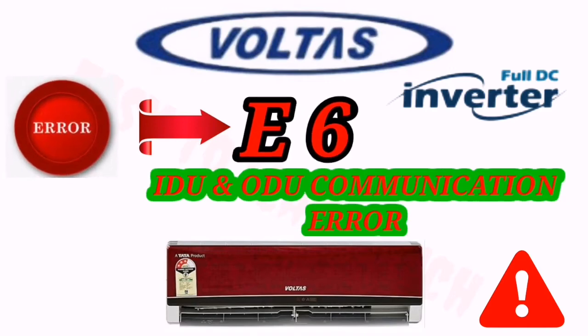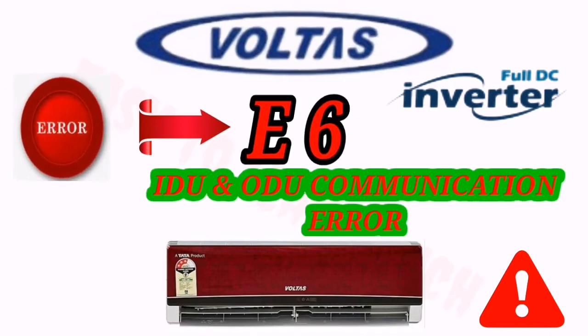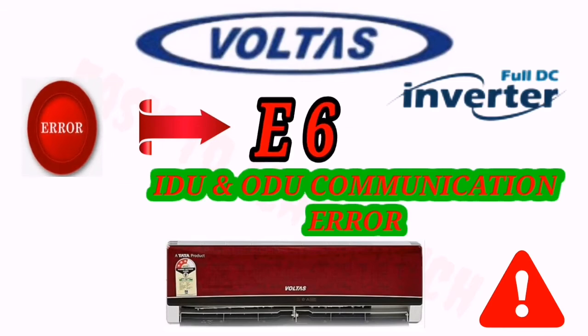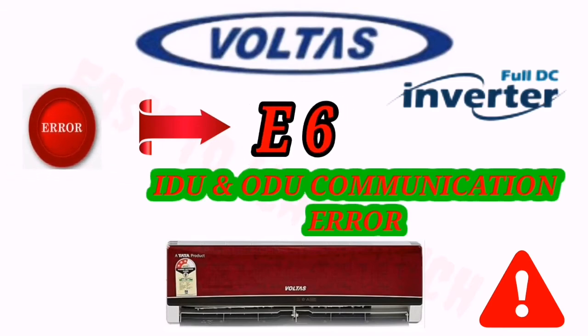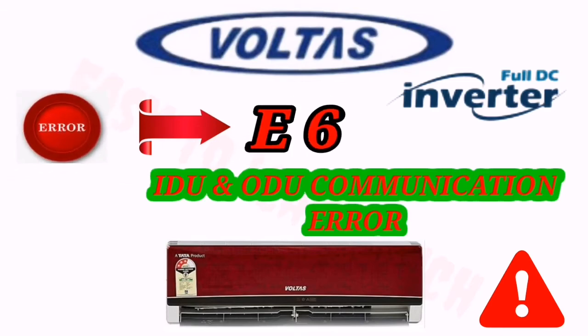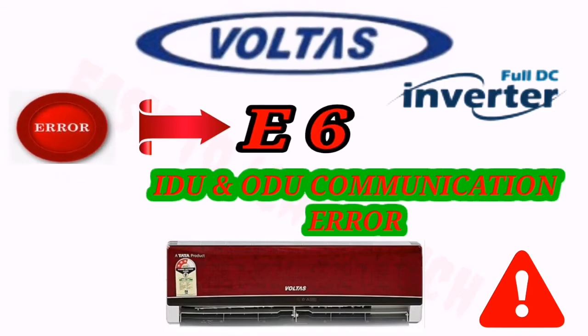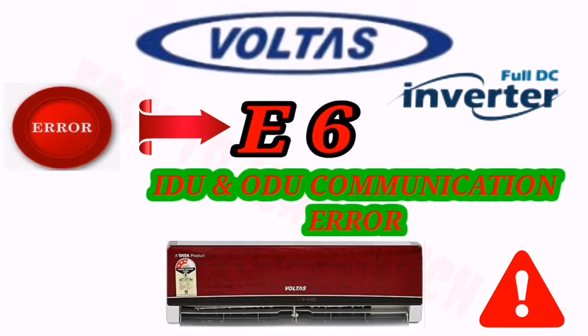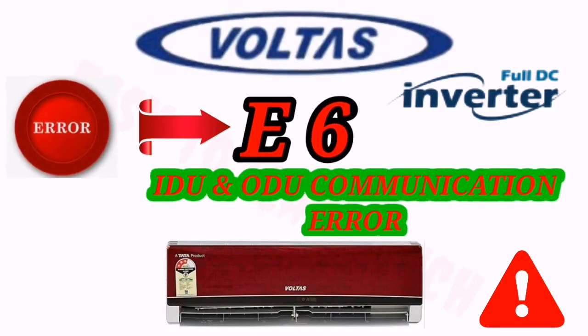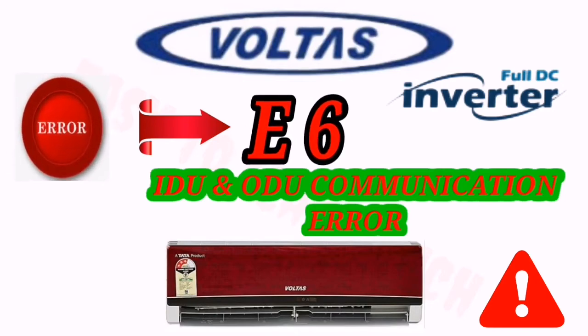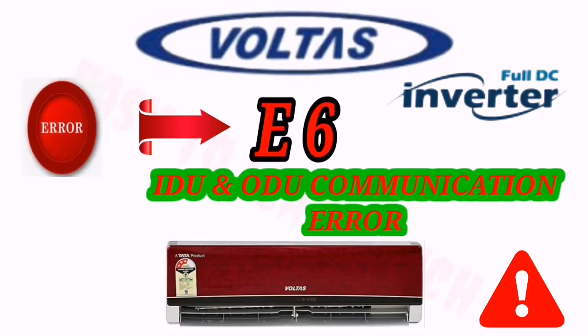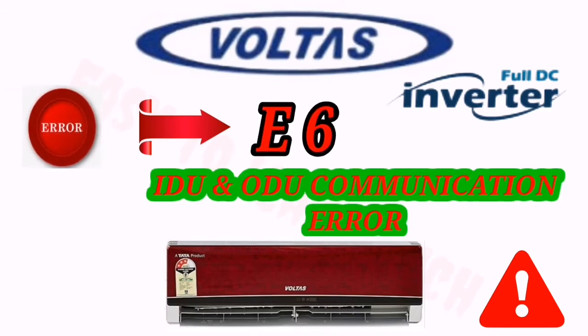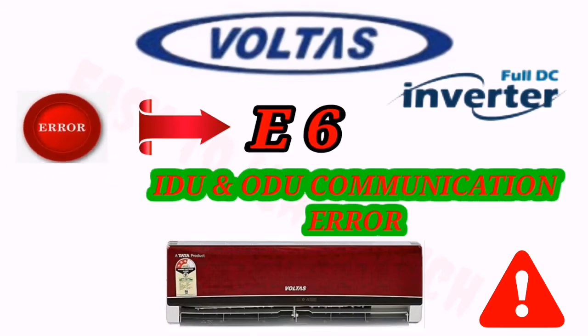And again, if you are getting the same error, then you have to check the output supply from the communication cable which is coming from the outdoor unit to the indoor unit. Remove the cable from the indoor unit and check the communication. The voltage should be between 13 DC and 24 DC. If it is between that, it means our outdoor PCB is giving the command and our indoor PCB is not giving the command. At that time, you have to change the indoor PCB.